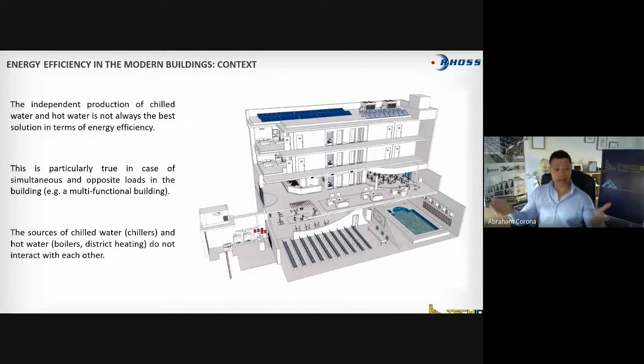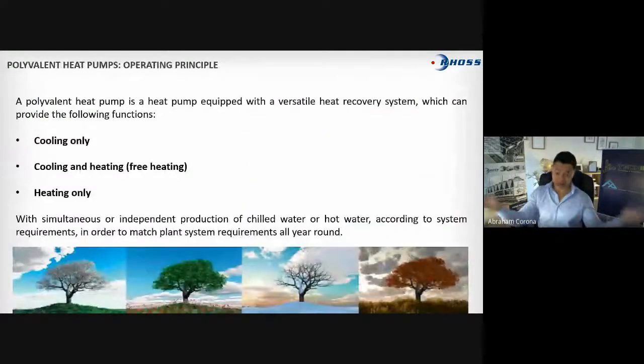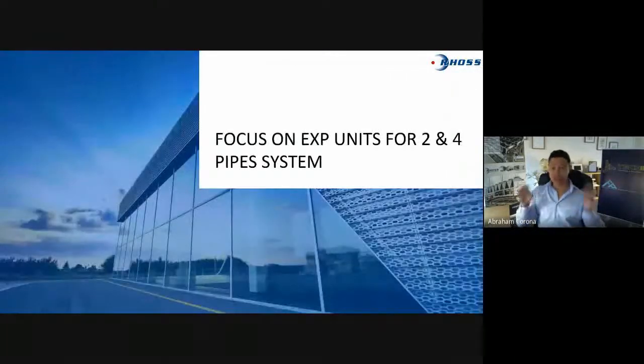So how a 4-pipe EXP system works is exactly that: when you're trying to combine independent or simultaneous cooling and heating demand. That's exactly what an EXP is here. An EXP unit is no more than what we call a smart heat pump with smart heat recovery, where you can get cooling only, heating only, or cooling and heating in any season, winter or summer, and it will be done automatically by the machine. All right, so keep that in mind. You're going to have complete satisfaction, and you're going to be meeting capacity for heating and cooling, independent or simultaneous. So let's go to the basics.